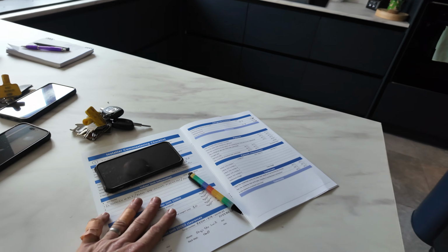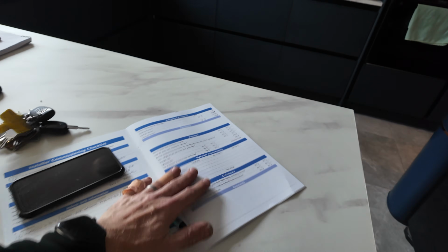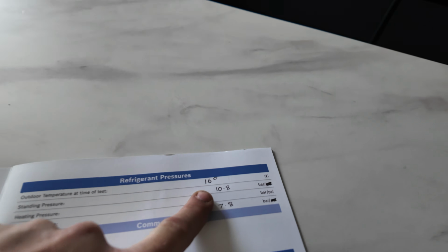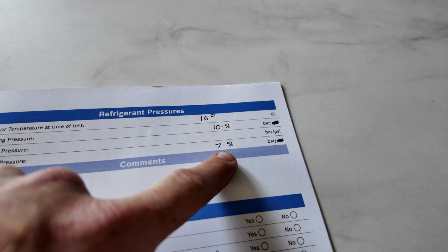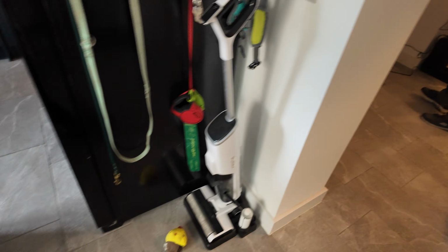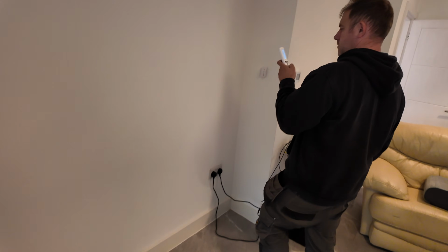But yeah, let's run through testing, commissioning, stuff like that now, and make sure this is actually running as it's supposed to be. So we've got our own commissioning checklist that we do. On there it's going to ask you refrigerant pressures, so we've done standing was 10.8, cooling was 7.8. But what we're doing now is the temperature on cooling.